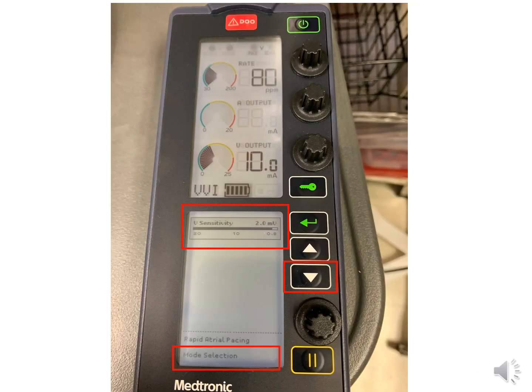Now looking at the second half of the pacemaker box, the lower part will open up some additional menus. The first one you see is the sensitivity, and that's right next to the green arrow. Here the ventricular sensitivity is set at 2.0 millivolts. The other extra menu you may see is the mode selection, and to get to the mode selection, what you would do is you would go down on the white arrow till you get to your mode selection.